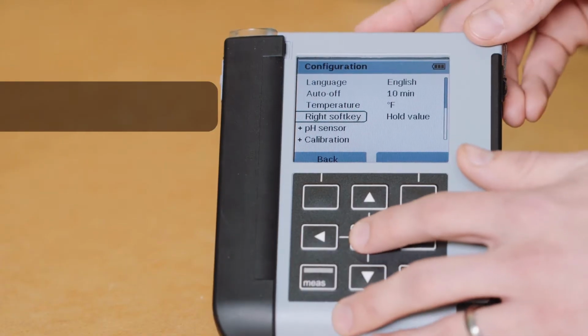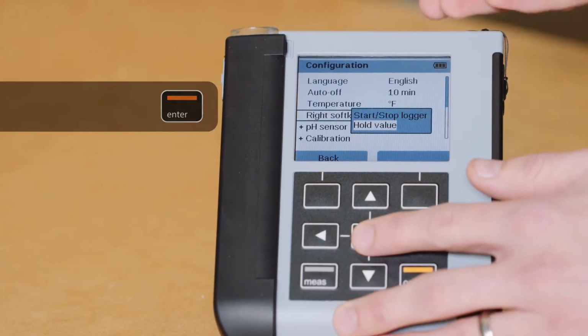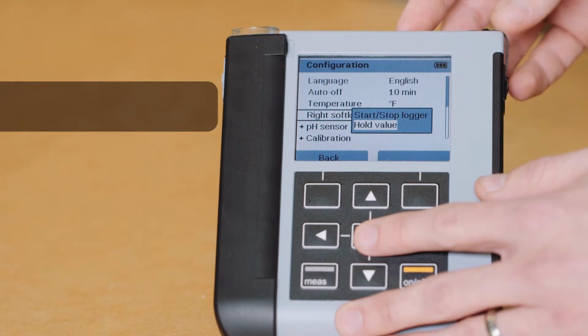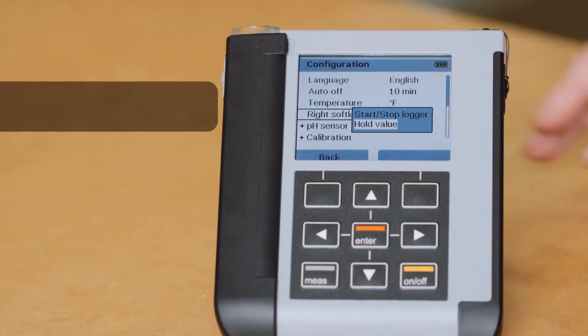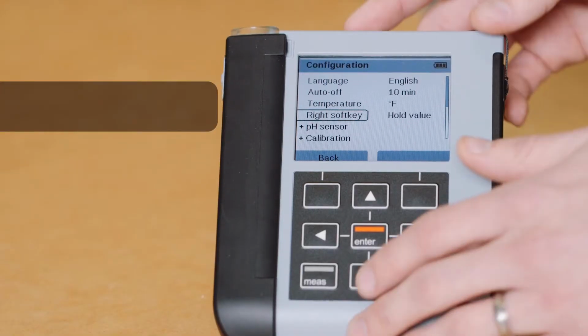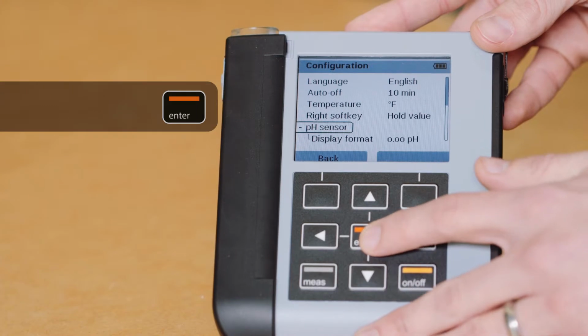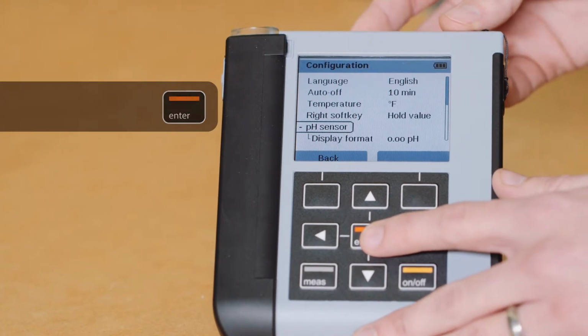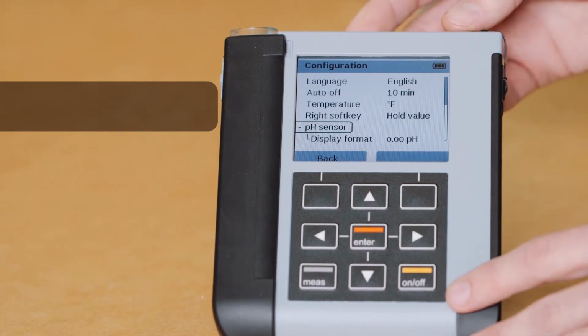Next, you can choose the function of the right soft key on the main display screen. You have two choices here. You can start and stop the data logger or hold the measured value. The next feature is for the display type of the measurement which you are making. In this instance, we have pH. Here, you can select the number of digits after the decimal point of the measured value.